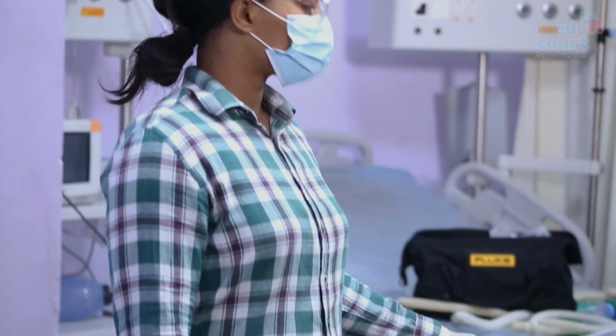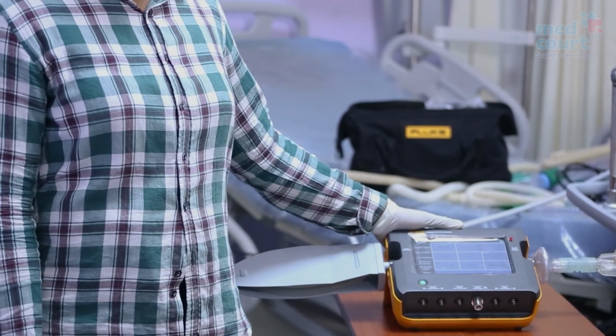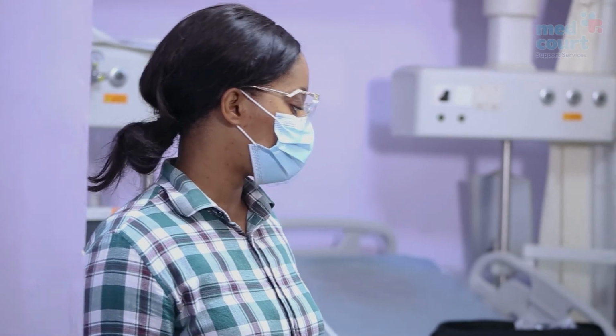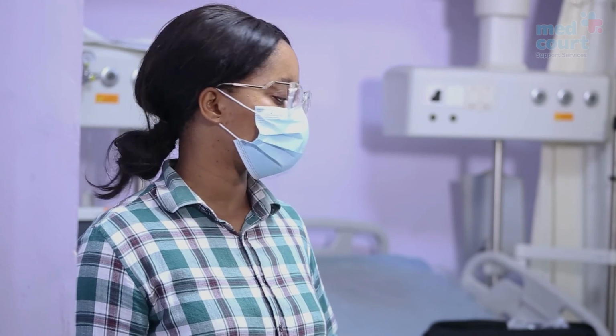We have come to the end of this demonstration session. As mentioned earlier, ensure that all values on the VT900A are in close proximity to the value set on the ventilator, for instance, the percentage oxygen set. If there is a large disparity, ensure that the oxygen sensor of the ventilator is checked. If expired, do replace. In addition, the PEEP setting on the ventilator should also be in close proximity with the values displayed on the VT900A. If there is also a large disparity, the test lung can be replaced, as the resistance of the test lung may have reduced over time.